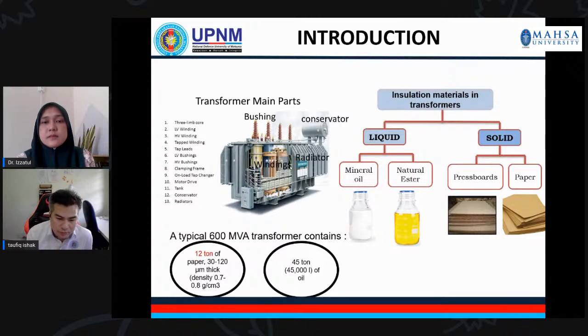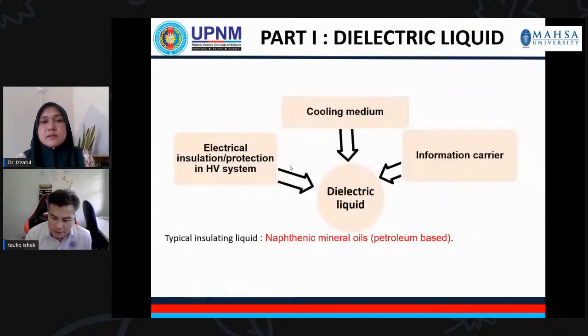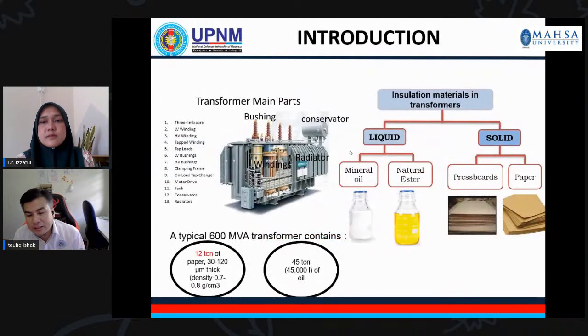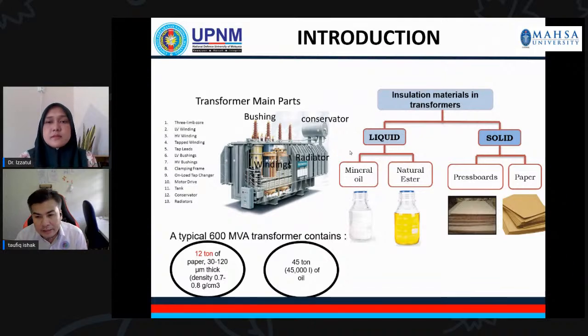Besides the liquid, we have solid insulation, which can be divided into major and minor insulation structures. The major insulation inside the transformer consists of barriers, spacers and clamps, which we call pressboard, while the minor insulation consists of winding insulation paper, the cellulose. The function of the solid insulation is to serve as electrical insulation, and the second is to give support for the winding.